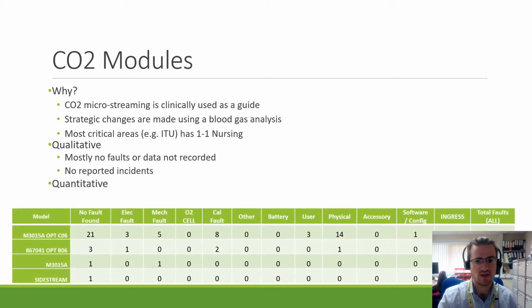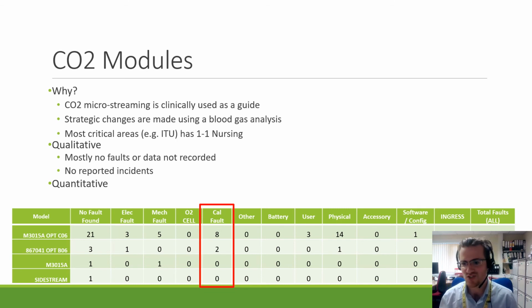Quantitative data, the PM checks, the calibration fault, is what we are going to use as the surveillance data. However, as mentioned, data wasn't being recorded. It seems manufacturer training changes, and what some techs are doing that others aren't, and they've been told to calibrate and then check the calibration rather than what was initially being rolled out, which is check, calibrate if necessary, and then check again. So data was being hidden.